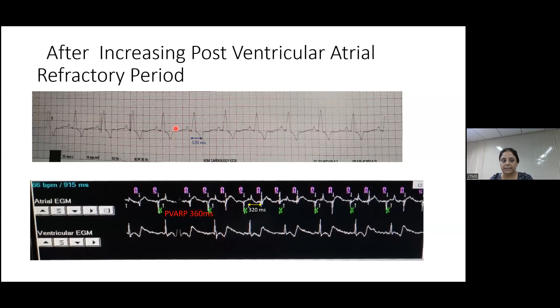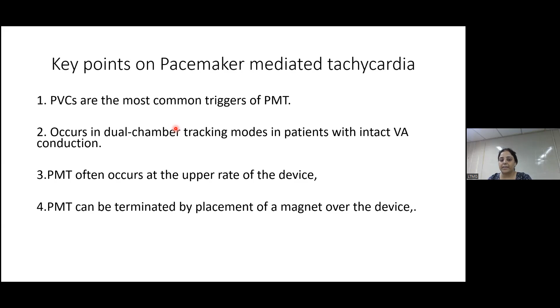The key points on pacemaker tachycardia: it occurs in the dual chamber tracking mode in patient with intact VA conduction. PVC are the most common trigger of the pacemaker tachycardia, but any condition which causes atrioventricular dissociation, either a PAC or atrial oversensing or undersensing, may produce this pacemaker mediated tachycardia. Pacemaker mediated tachycardia often occurs at the upper rate of the device, and it can be terminated by placing a magnet over the device, or we can easily terminate it by increasing the post-ventricular atrial refractory period. Thank you, sir.